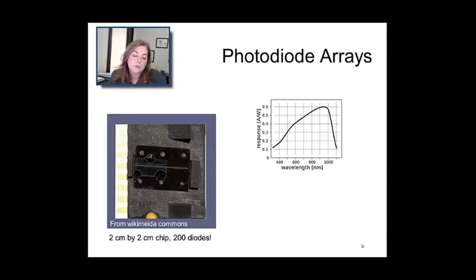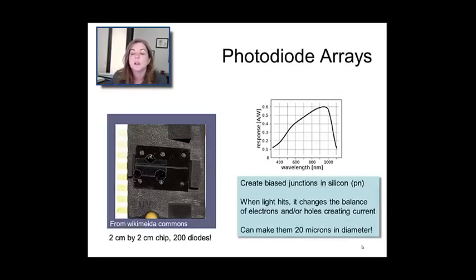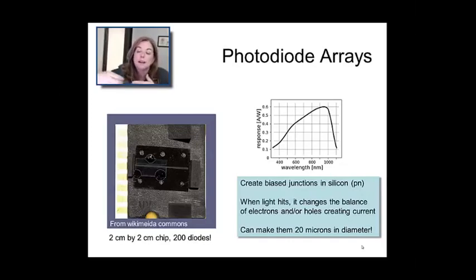If you've created a device structure in silicon, those carriers can modulate the electrical properties you're measuring. In this case, your junctions are biased. And that means that when light hits them, you're going to create a balance of electrons and holes that you're going to be able to detect. You're going to be able to say exactly how many electrons and holes you've created as a function of distance along this long, thin line. So it's an example of a kind of detector you can use for multi-channel detection. Photodiode array, because it's spatially spread out, can be matched to a grating that spreads out the light. So you don't have to rotate the grating. You keep it fixed. And the photodiode tells you all of the wavelengths present in your data. This is the PDA that we were talking about for the high-performance liquid chromatography systems. So it's really perfect for multi-channel detection. But it has really, really crummy photon detection capabilities like none. So it's not nearly as sensitive as a PMT tube.